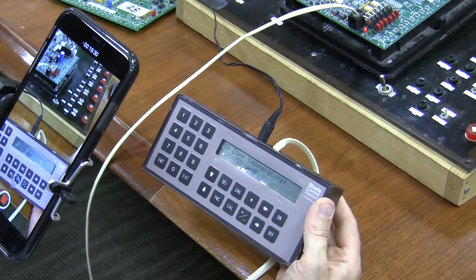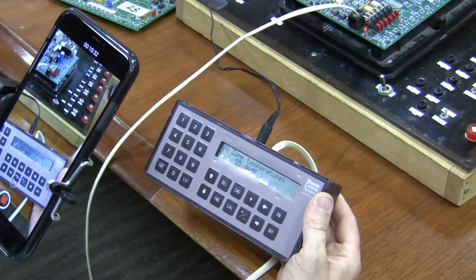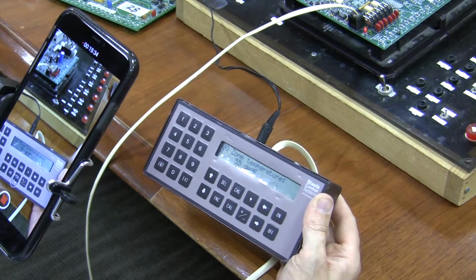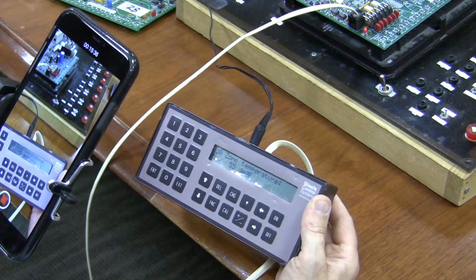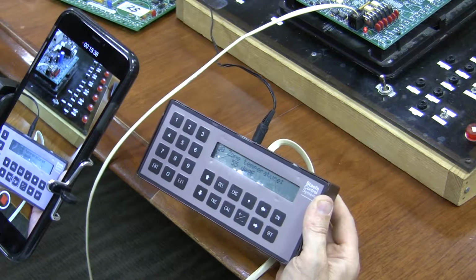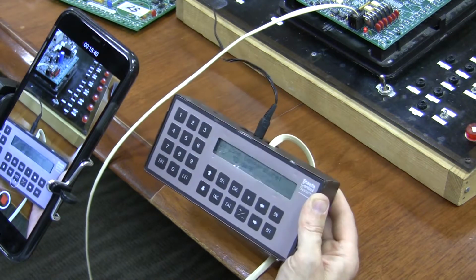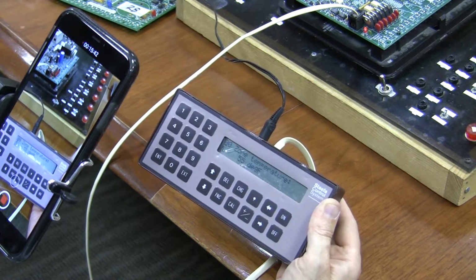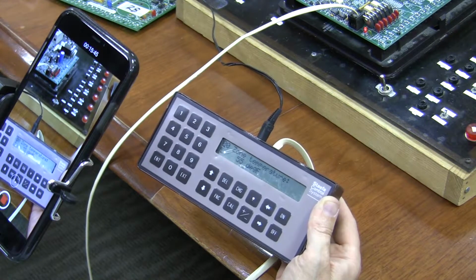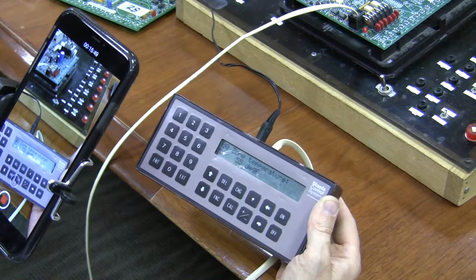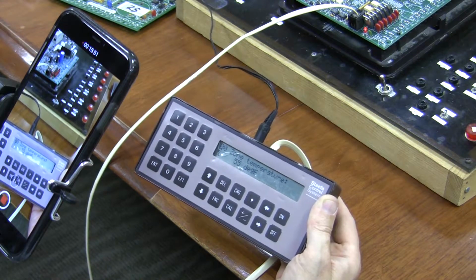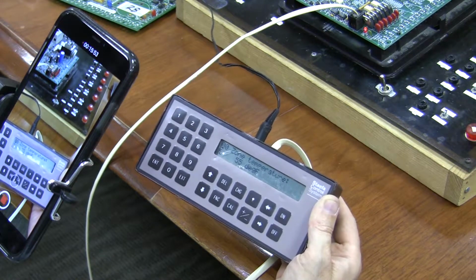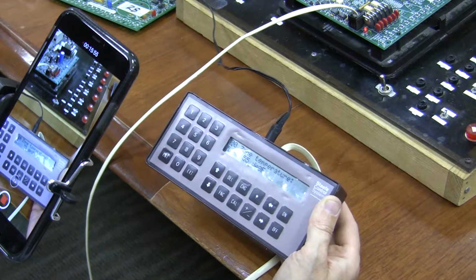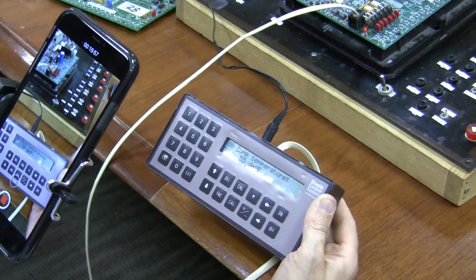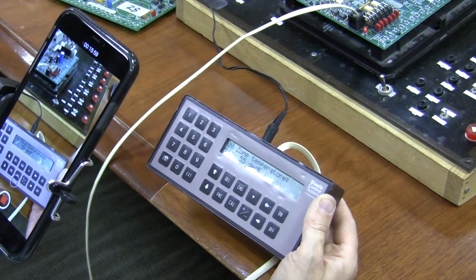Now I got to caution you. If it's off more than a degree or two, there's some other problem than calibration. Okay? But if it's just a degree or two, hey, it's really 70 degrees in here and this thing's thinking it's 72 degrees. So go ahead and plug in with a service tool, go to commissioning mode, hit the calibrate button, and calibrate it down. This is how the balancer also calibrates the airflow with this same exact process.